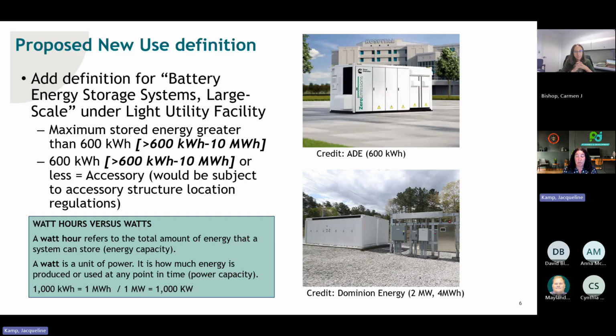Those systems with a maximum stored energy less than the threshold would then be considered an accessory use. The 600 kilowatt hour threshold comes from the National Fire Protection Association standard for energy storage, NFPA 855, which requires additional safety standards when a BESS site has a maximum stored energy greater than 600 kilowatt hours. And then we put the higher range of 10 megawatt hours as that comes from Dominion's model ordinance for battery energy storage systems.